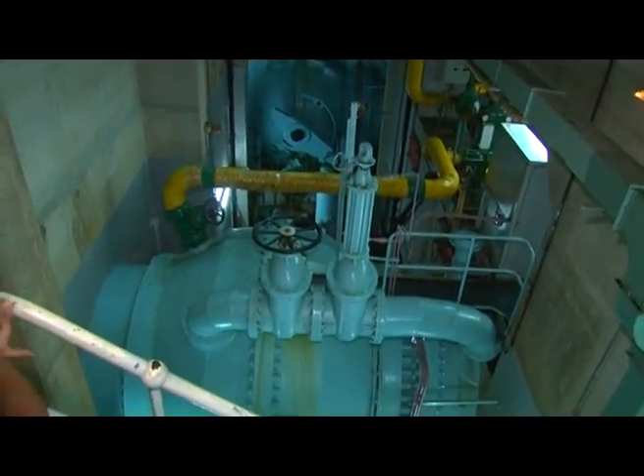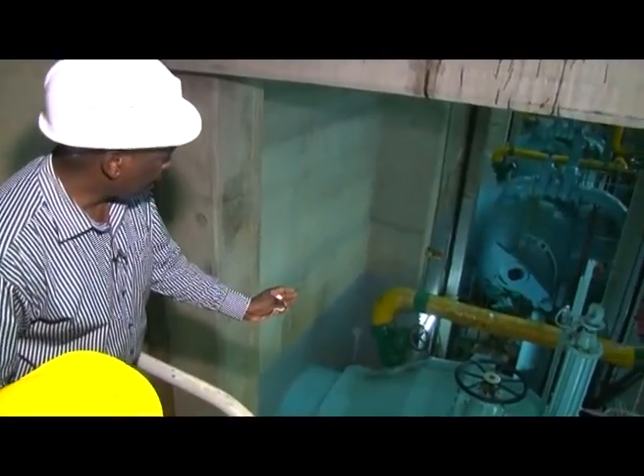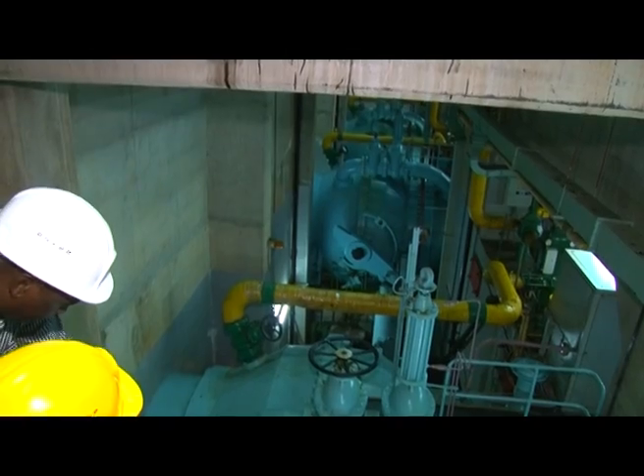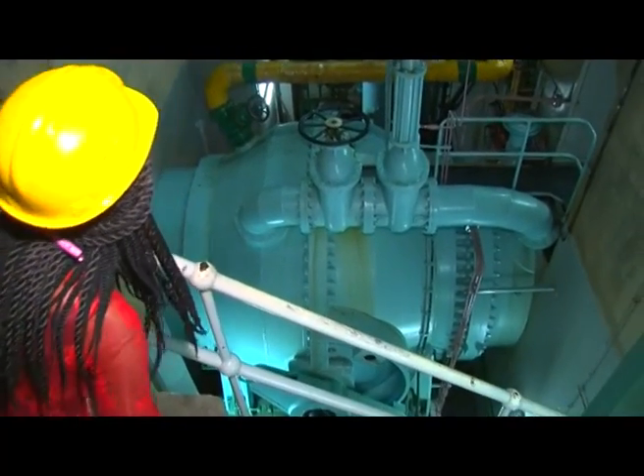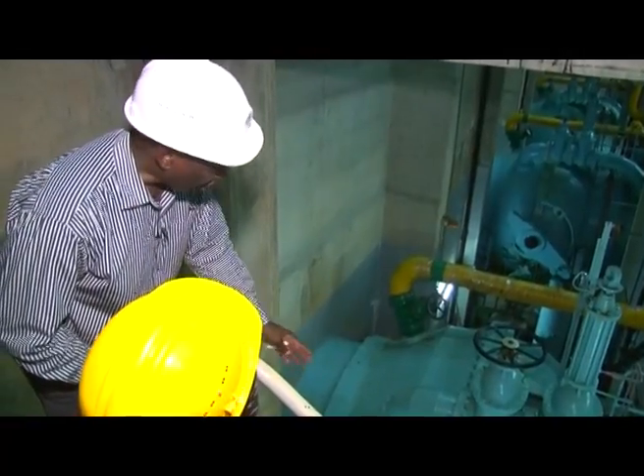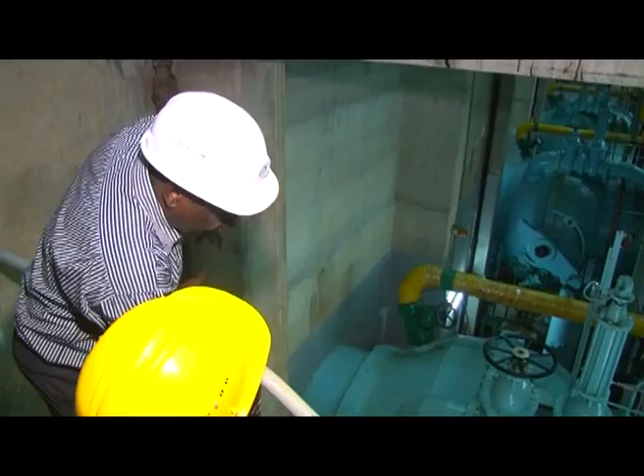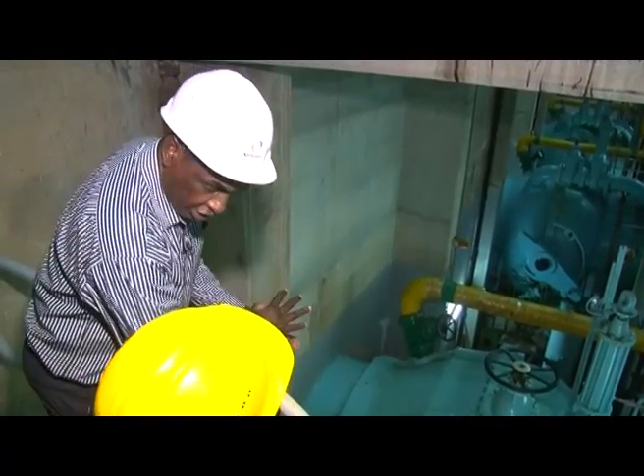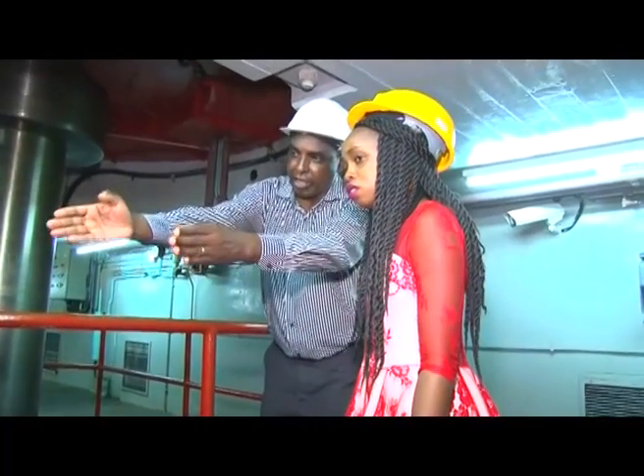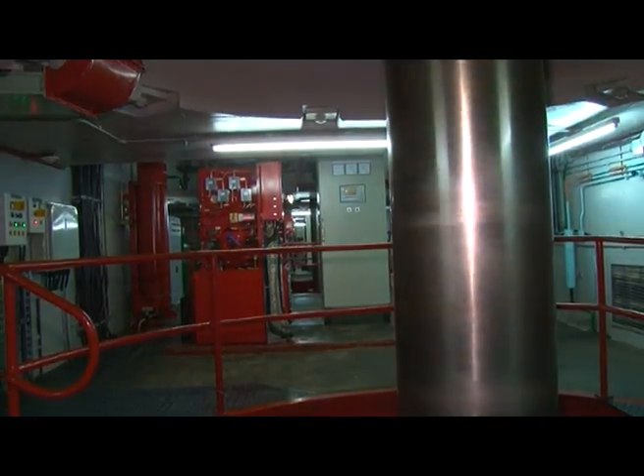When it comes to controlling the water passing through, here we only have a spherical valve so that when the machine is not running we can close it. You can see this arm here — this arm shows it is open. If you go to the extreme one you'll see its arm will be at a different angle because it is closed. The valve is actually a ball valve, or spherical valve — right now it's open so the water is running through. If you are carrying out maintenance you close it to stop the water from coming in. The water pipe is coming in here, it goes inside, and the water gets in from all the sides and rotates the machine.